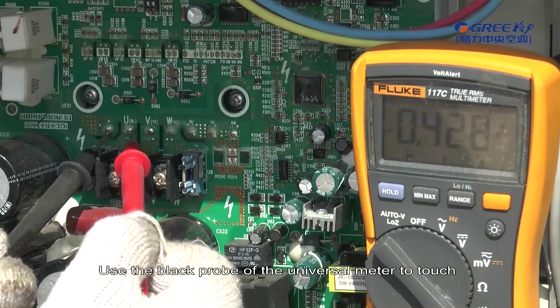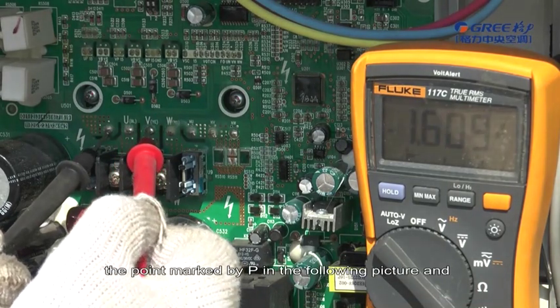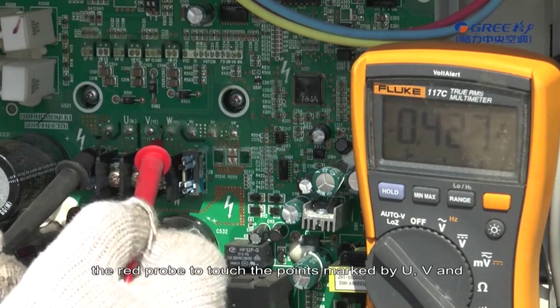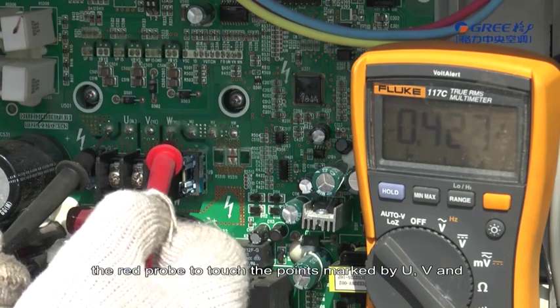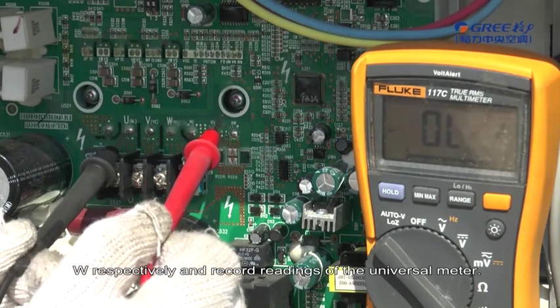Detection Method. Use the black probe of the universal meter to touch the point marked by P in the following picture and the red probe to touch the point marked by U, V, and W respectively. Record readings of the universal meter.